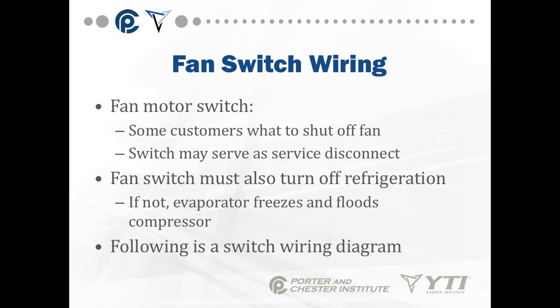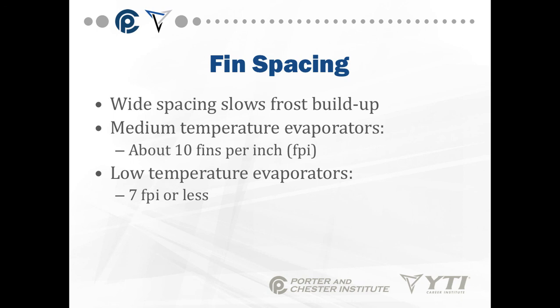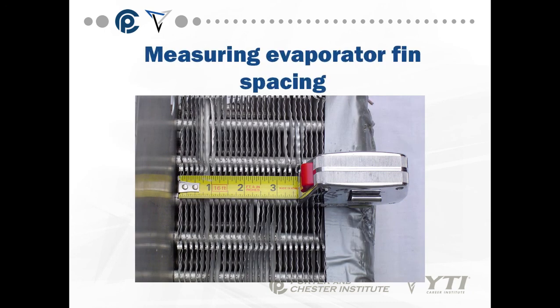For fan switch wiring, some customers want to shut off the fan, and the switch may serve as a service disconnect. The fan switch must also turn off the refrigeration — if not, your evaporator freezes and floods the compressor. Wide spacing of fins slows frost buildup. Medium temperature evaporators have about 10 fins per inch; low temperature evaporators have 7 fins per inch or less. The lower the temperature, the wider the fin spacing. You can measure evaporator fin spacing to confirm the correct evaporator is being used.